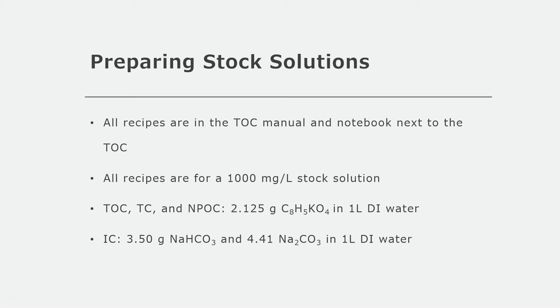These stock solution recipes are for 1,000 mg per liter solutions that can be diluted for your calibration curve. To make the stock for TOC, TC, and NPOC, you'll dissolve 2.125 grams of potassium hydrogen phthalate in 1 liter of DI water. And for inorganic carbon, you will dissolve 3.5 grams of sodium bicarbonate and 4.41 grams of sodium carbonate in 1 liter of DI water.